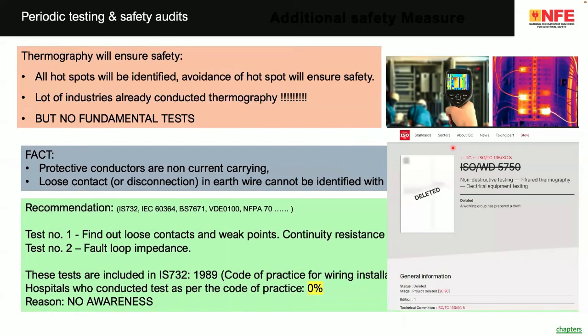But what we do is thermography. Unfortunately, whenever I say thermography is not a recognized electrical safety measure, a lot of people object, because a good electrical installation is not supposed to have hotspots. You make a perfect electrical installation so that there is no loose contact and no hotspot. If you have a building or a hospital, and there are hotspots inside your panel board, it means your installation is not in compliance with the standard. So you are in an extremely dangerous situation.